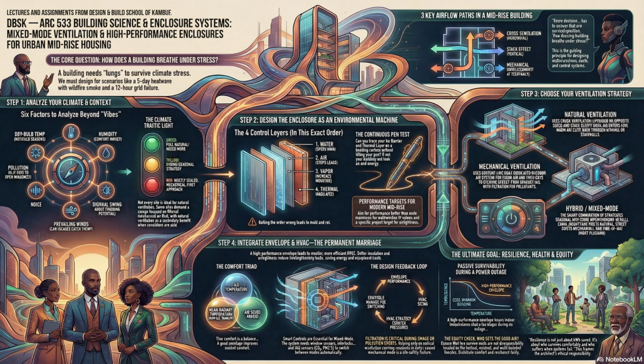That's your green arrows. And then mode 3, emergency resilience. This is triggered by high PM2.5 from wildfire smoke or an extreme heat event. Windows are locked or strongly advised to be closed. The system shifts to maximum filtration, MERV 13 plus on the DOAS supply, and crucially, it often slightly pressurizes the interior spaces. Why the pressurization? When you slightly pressurize the interior, any remaining small cracks or leaks in your air barrier will force air out of the building. This prevents unfiltered dirty air from being sucked in from the outside. So that intentional marriage of systems means your high-performance wall becomes the container and your HVAC system becomes the controlled air pump, guaranteeing safe indoor air quality when Eleanor on the 5th floor needs it the most.